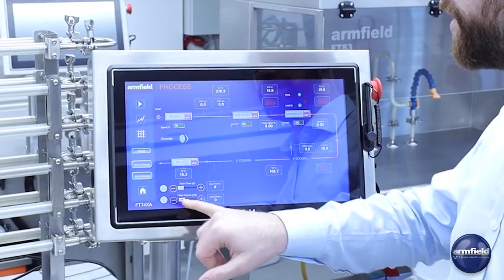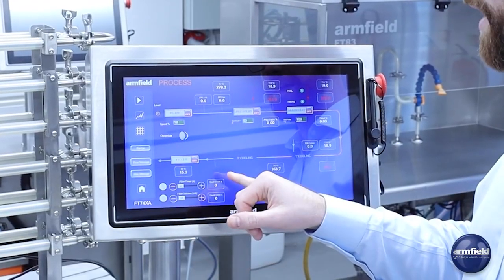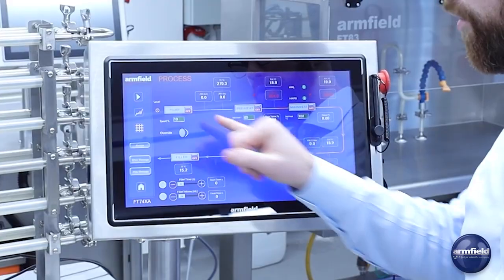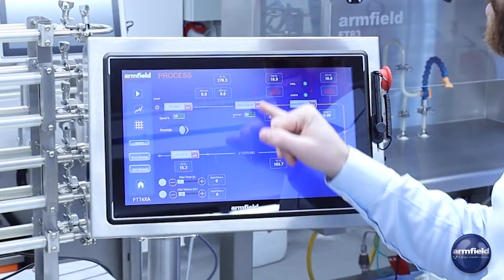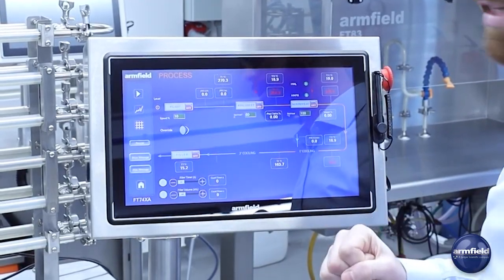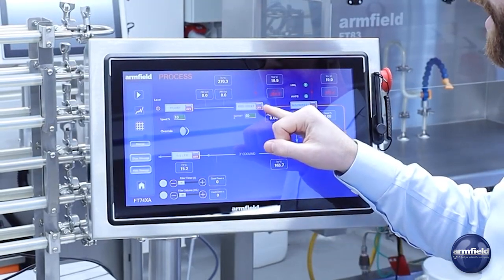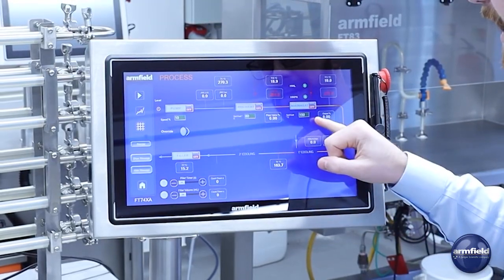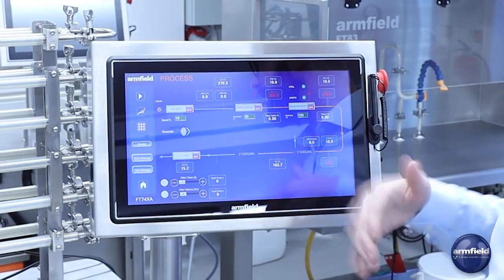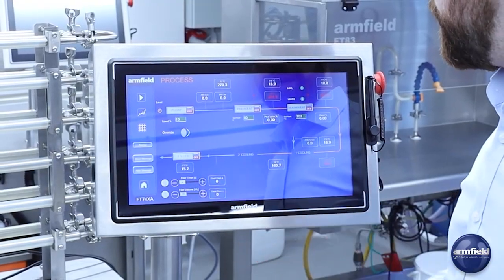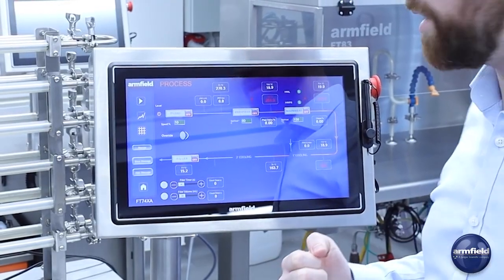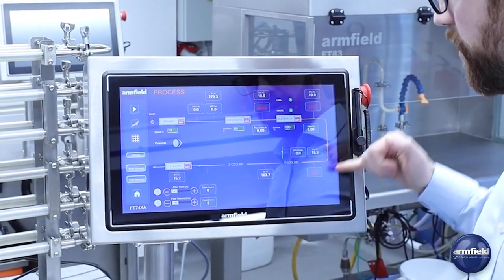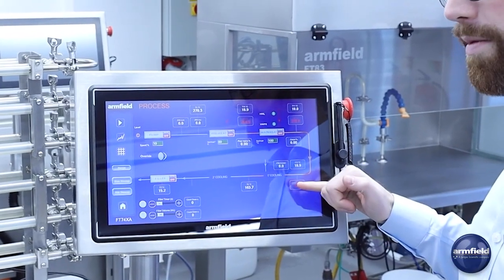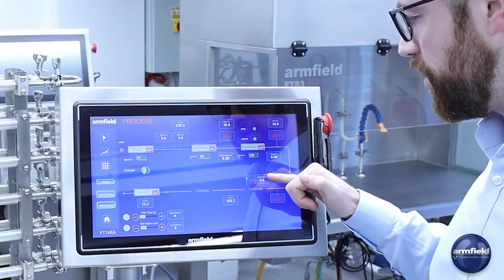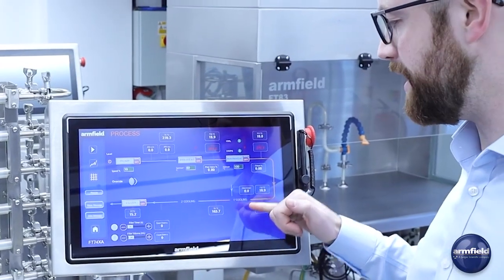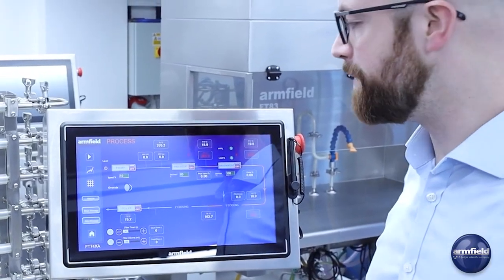So moving to the process mode, you then get the controls popping up there that you can see. So you can turn the pump on and off and set the speed, you can override it, you can see the flow, the pressure, the temperature as it comes in. You can see the preheat controls, the main heat controls. You can see that there's warning lights. If they're red, then obviously you can't process. And then that just gives a cue to the operator to have another look at what's going on. And then you can see obviously the holding tube again and the cooling water flow rate going in, and then the impact that has on the process temperature.